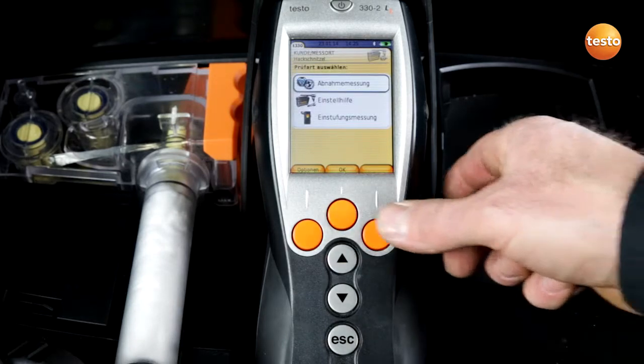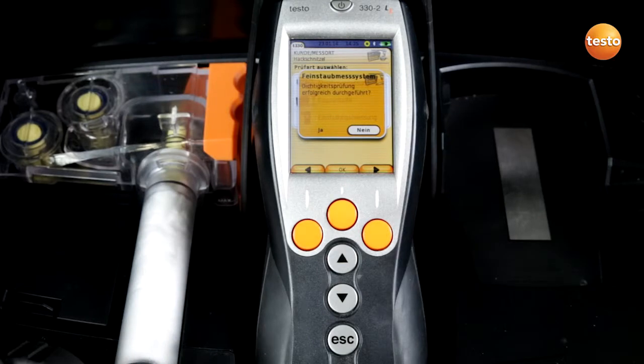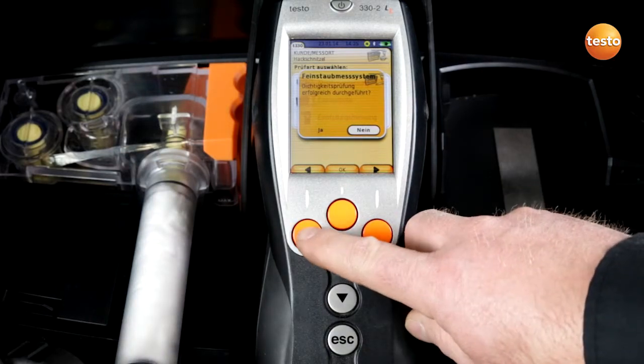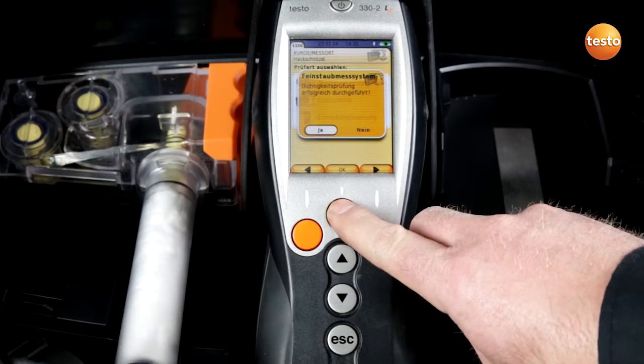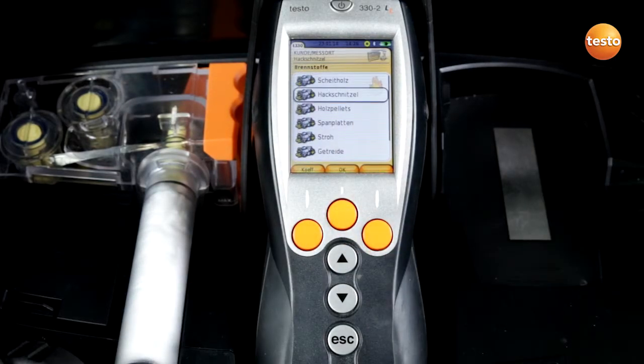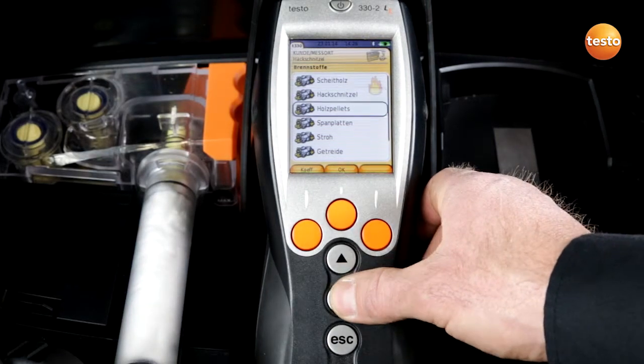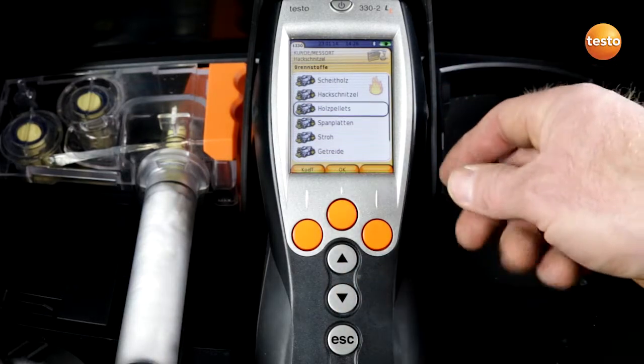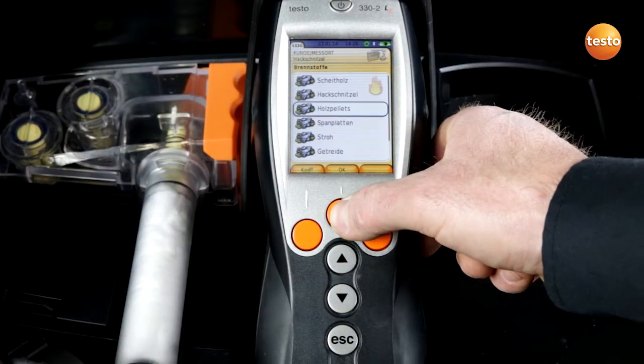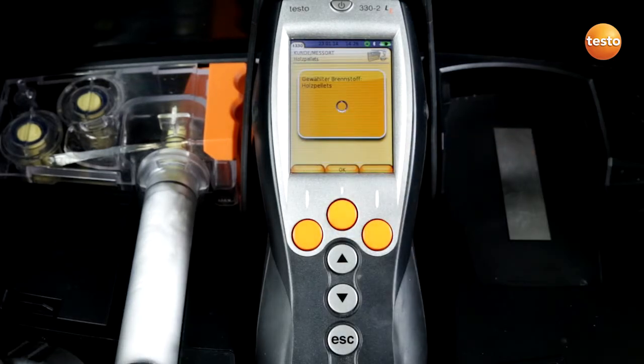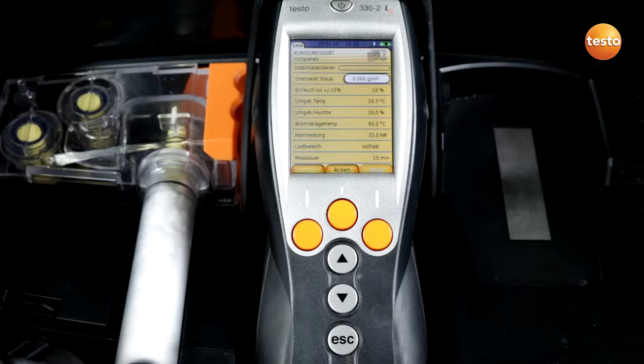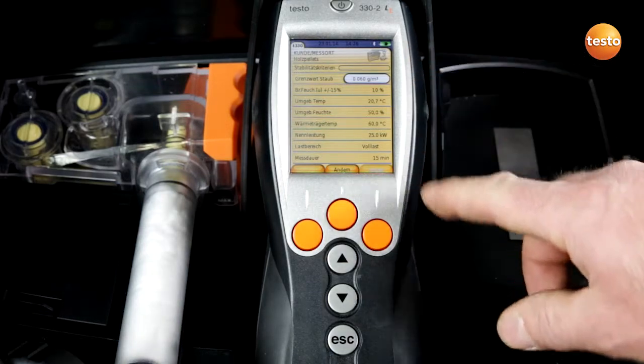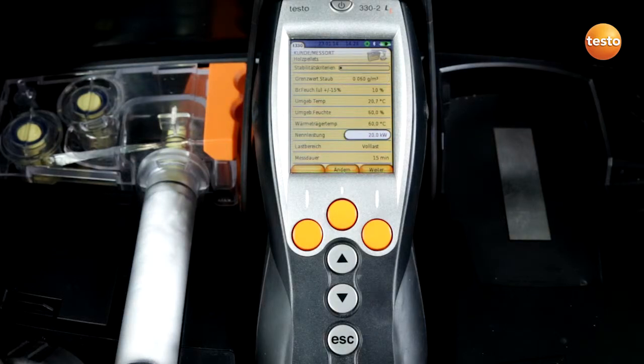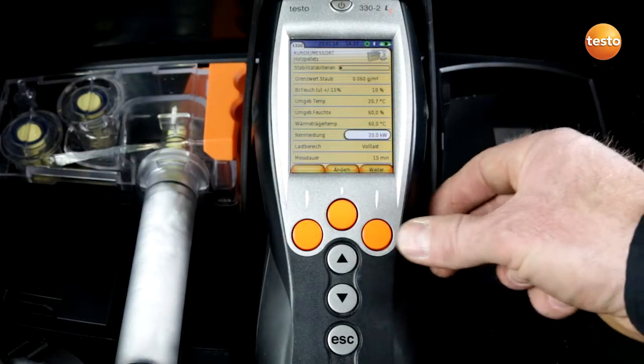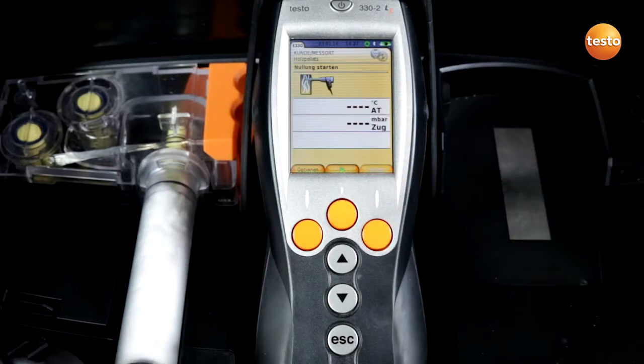I then go back to acceptance inspection and can confirm that the tightness test has been carried out successfully. Following this, I select a fuel. I can move down with the arrow and confirm that we are dealing with wood pellets, and confirm with OK. During the stabilization time, I can adjust the individual parameters.